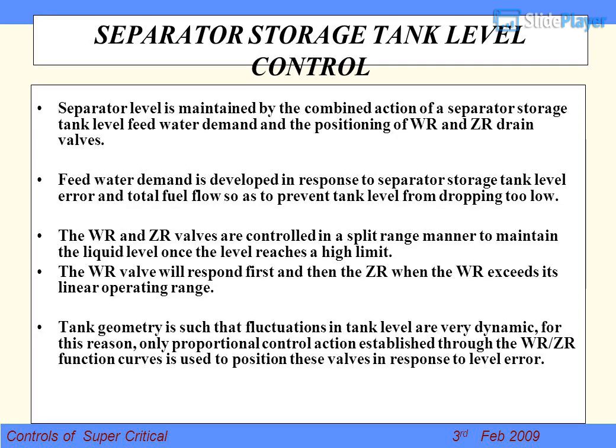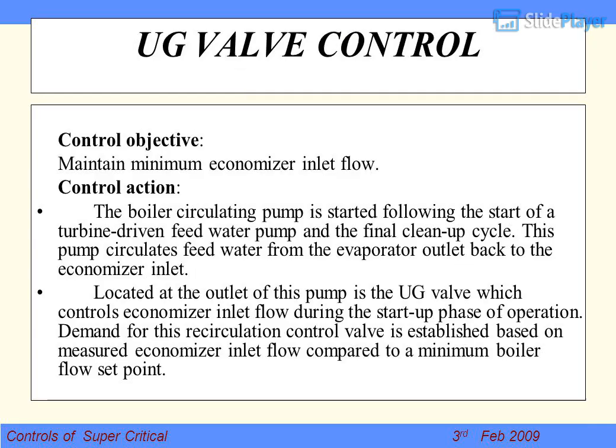Separator Storage Tank Level Control: separator level is maintained by the combined action of separator storage tank level, feed water demand, and the positioning of WR and ZR drain valves. Feed water demand is developed in response to separator storage tank level error and total fuel flow, so as to prevent tank level from dropping too low. The WR and ZR valves are controlled in a split-range manner to maintain liquid level once the level reaches a high limit. The WR valve responds first, then the ZR when WR exceeds its linear operating range. Tank geometry is such that fluctuations in tank level are very dynamic; only proportional control action through the WR/ZR function curves is used to position these valves in response to level error. SP level is maintained, and feed water demand is trimmed by separator level.